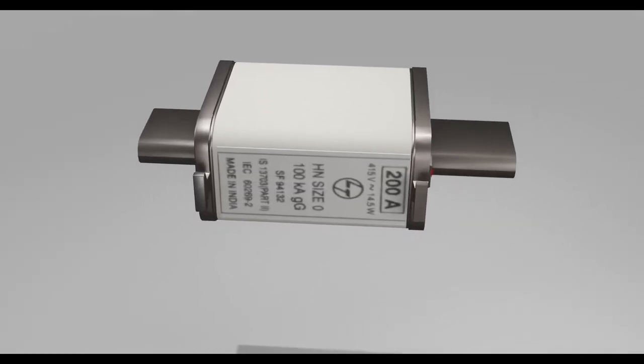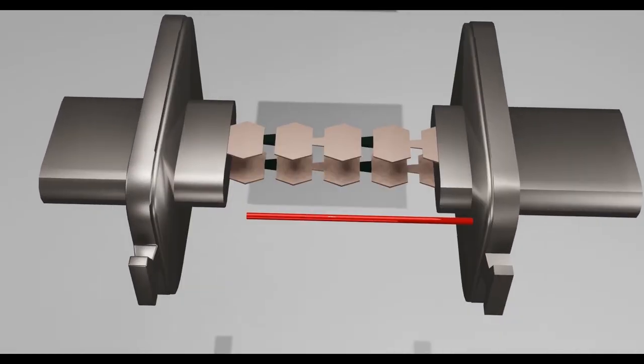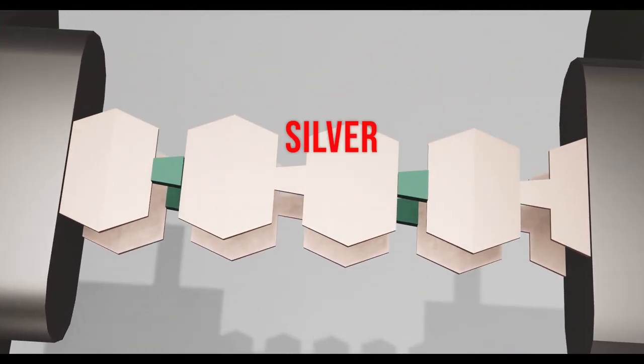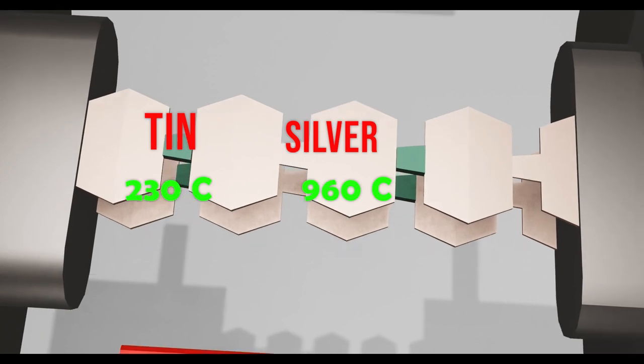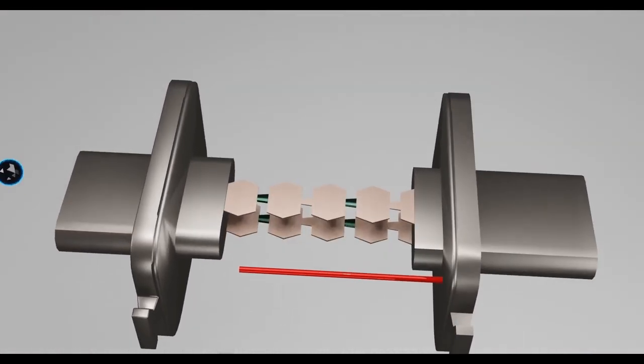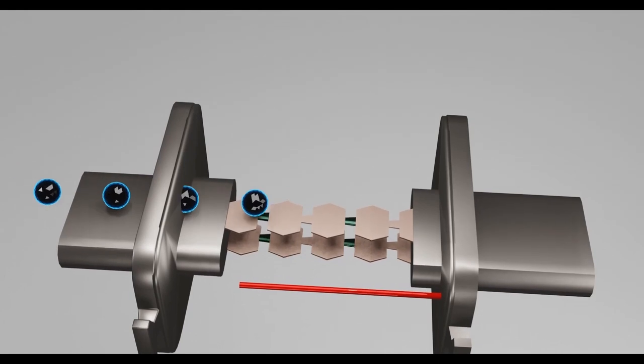us discuss the working of HRC fuse. As we discussed, the fuse element is made up of two materials, silver and tin. Silver has a melting point of 960 degrees Celsius, and tin has a melting point of 230 degrees Celsius.